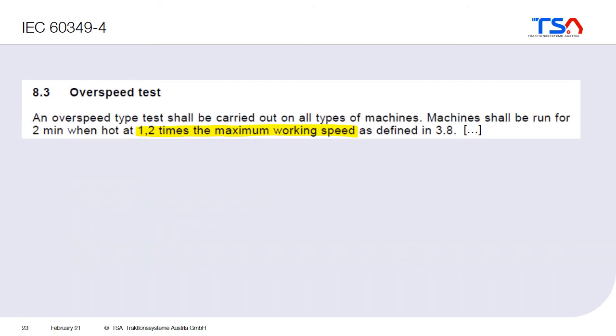To check if the machine is mechanically okay, an overspeed test is conducted. This is always done at 1.2 times the maximum working speed, and afterwards the machine is usually disassembled and checked.